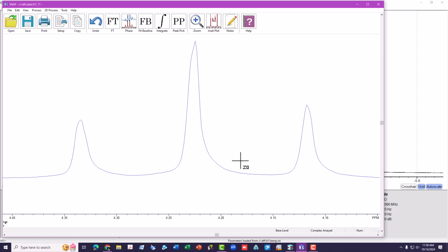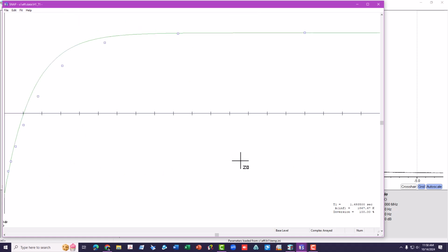We're going to type DR, like display relaxation data. And what you get is you get the fit function that it's going to use, but not fit yet, and then all the data points in this nice exponential function. And then finally, you can use, under the fit pull-down menu, notice you can just type the letter O or click right there, and then it'll fit. And you can look, the T1 down in the bottom right-hand corner here, it listed as 2 seconds.